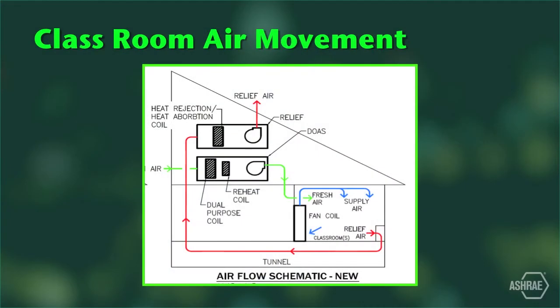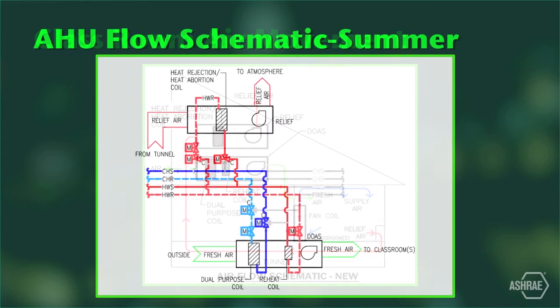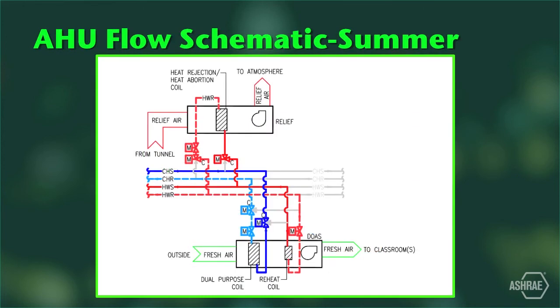The deep energy solution was a 2-coil DOAS unit with a changeover heating and cooling coil and a downstream reheat coil, and a corresponding heat recovery heat rejection coil in the relief air path. That part is similar to a runaround coil. Here's the piping for the DOAS unit and the relief air unit for summertime, with the DOAS unit cooling with the first coil and reheating with the second. There are 4 3-way reversing valves, and there is a control valve at each coil. The relief unit is connected to the heating water loop.